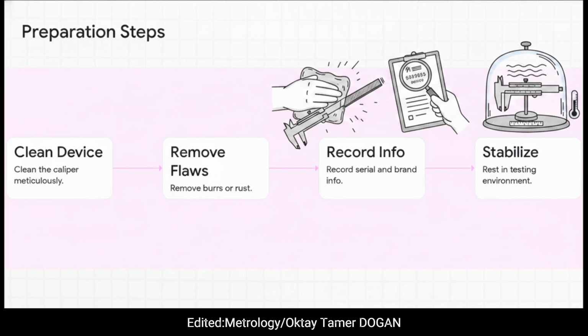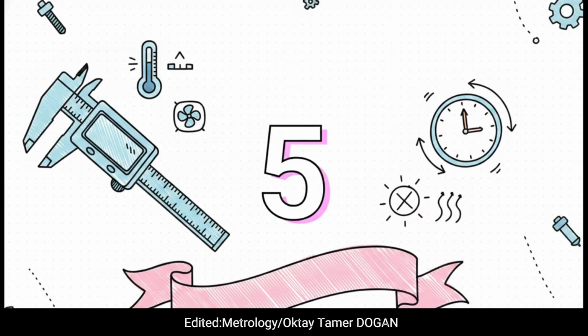If it's analog, those lines better be crisp. If it's digital, the screen better be flawless. Then comes step 4, carefully moving the device into the testing environment. Which brings us to this massive number right here, 5 hours. You cannot, and I mean cannot, just yank a caliper off a hot factory floor or out of a freezing delivery truck and test it. It has to sit in a stable, temperature-controlled room, away from drafts or direct light, for exactly 5 hours before calibration. Think about it. If you skip this thermal stabilization, your steel device is literally expanding or contracting while you're trying to measure it at the micrometer level. If that happens, your data is completely, undeniably invalid.